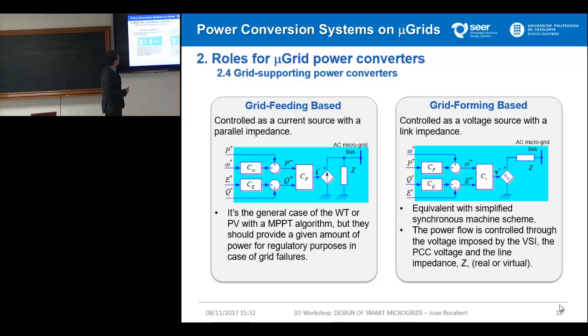It's the most typical, okay, where we get a power and Q reference, and this P and Q reference can be modified in the case of the droop equations. If we get some modification from the reference frequency or from the reference voltage level, we are going to give an extra P or extra Q, which can be positive or negative, in order to restore the grid conditions to their operation level.